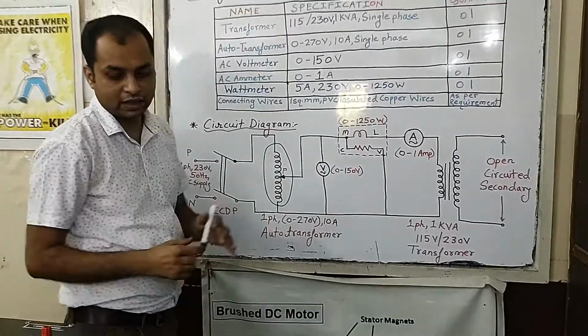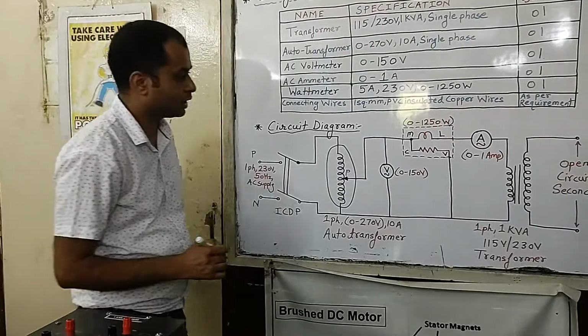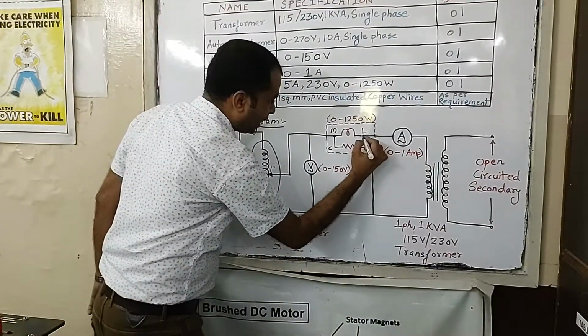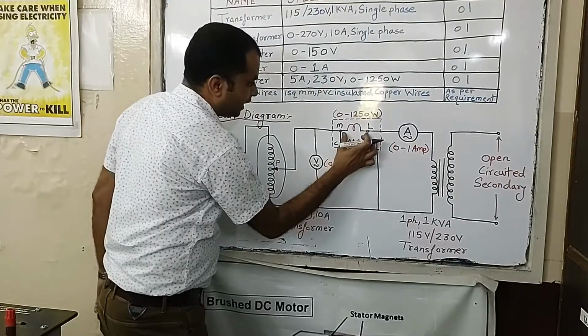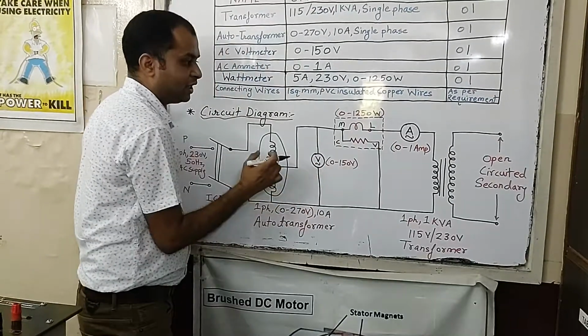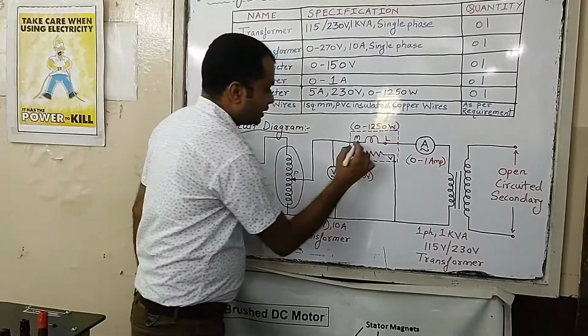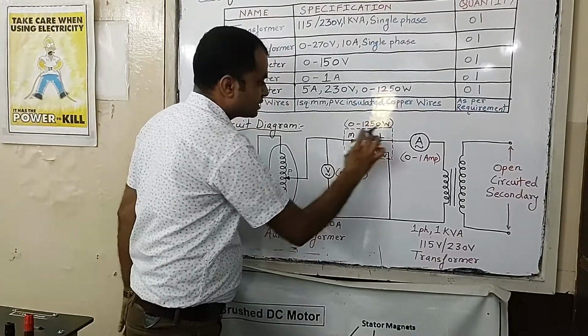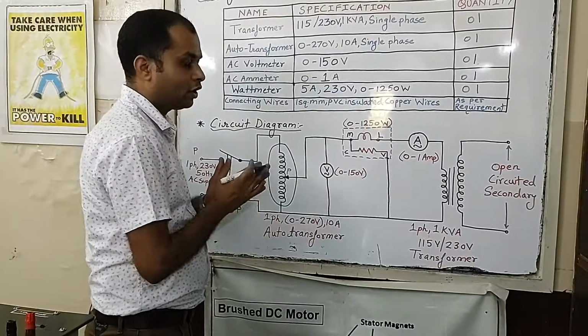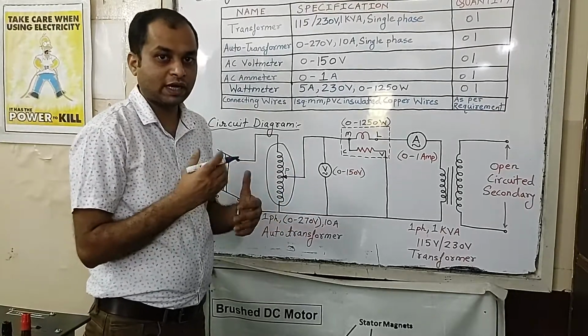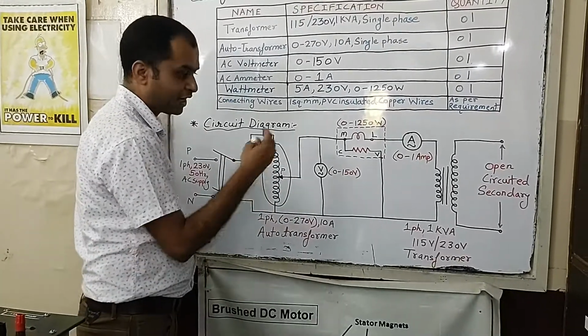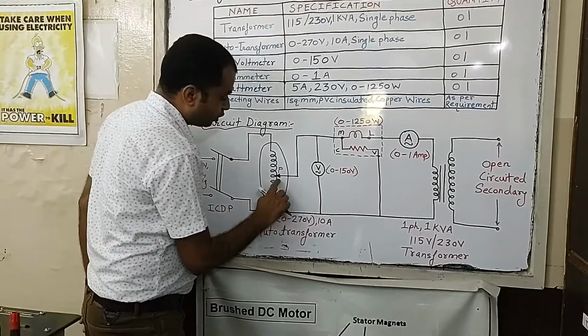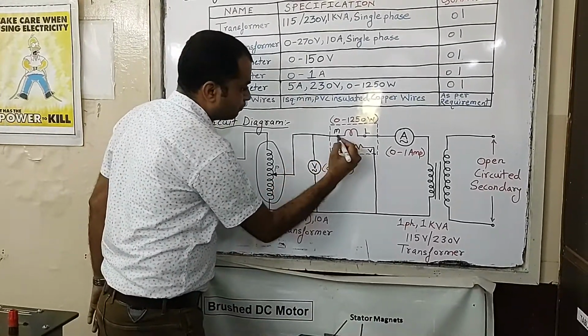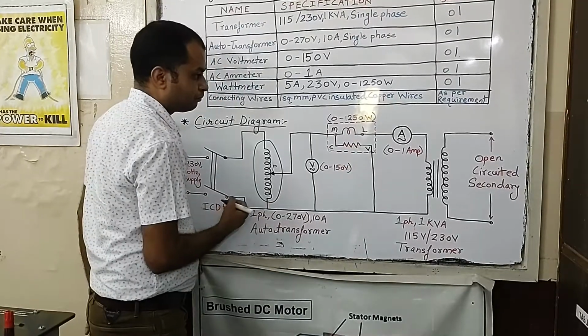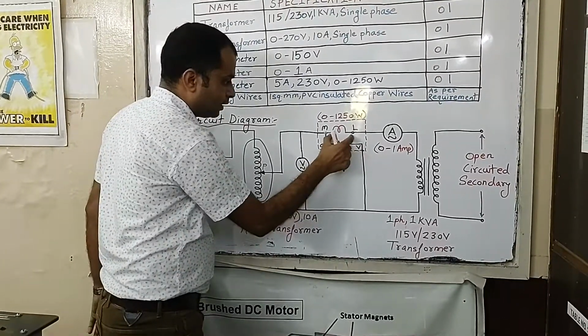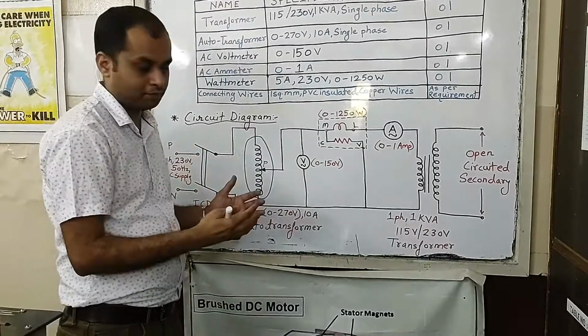As I told, in the wattmeter there are two coils. Here we can see M and L written. In that we have indicated one coil, which is the current coil. This is the current coil which will perform the task of measuring the current, and obviously we have to connect it in series. So how will we bring it into the circuit? The output of the auto transformer we will connect to the main terminal of the wattmeter, and M and L are internally connected.